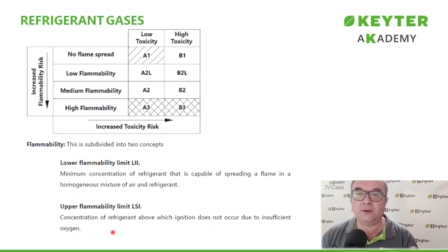Based on flammability, there are three categories. Category 1 includes non-propagating refrigerants tested at 60 degrees Celsius and 1 atm. Category 2 must meet three characteristics: show flame propagation when tested at 60 degrees Celsius and 1 atmosphere, have a lower flammability limit greater than 3.5%, which means it is necessary for it to have a moderately high concentration to produce that flammability, and also have a heat of combustion lower than 19,000 kilojoules per kilogram.